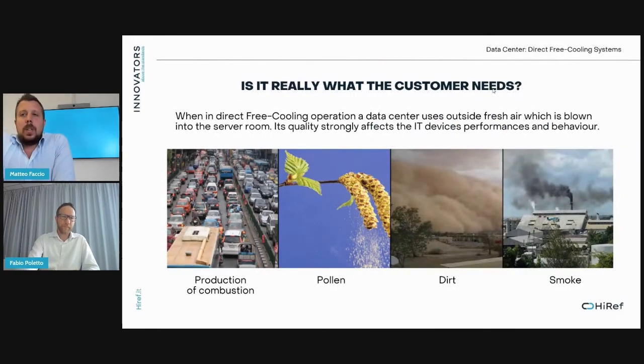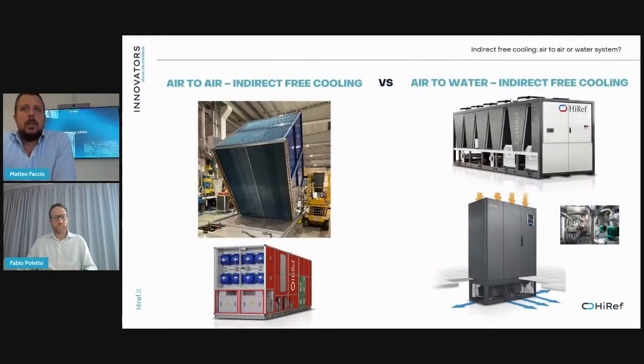With direct free cooling, we have the risk of bringing inside the data center a lot of substances, such as smoke, products of combustion, chemical components, and dirt. To avoid this and to make the system run properly using direct free cooling, it's required to add additional filters and additional monitoring systems, which all affect the data center efficiency in a negative way. I think we need to focus our attention in this talk on indirect free cooling.